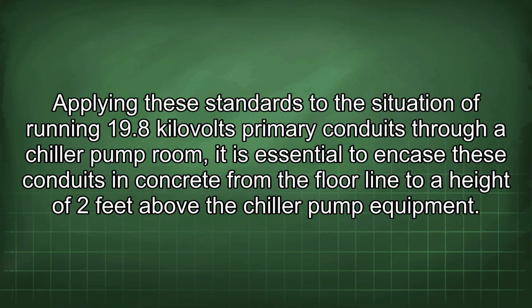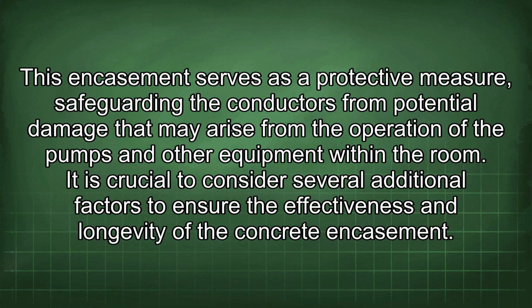Applying these standards to the situation of running 19.8 kV primary conduits through a chiller pump room, it is essential to encase these conduits in concrete from the floor line to a height of 2 feet above the chiller pump equipment. This encasement serves as a protective measure, safeguarding the conductors from potential damage that may arise from the operation of the pumps and other equipment within the room.